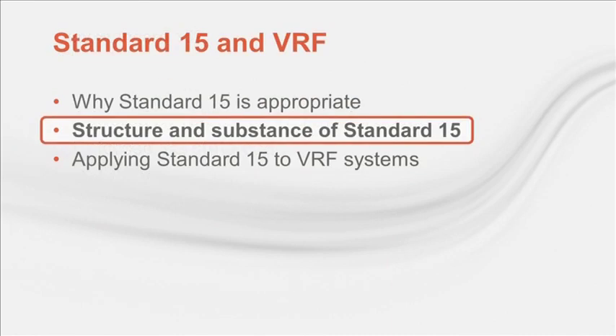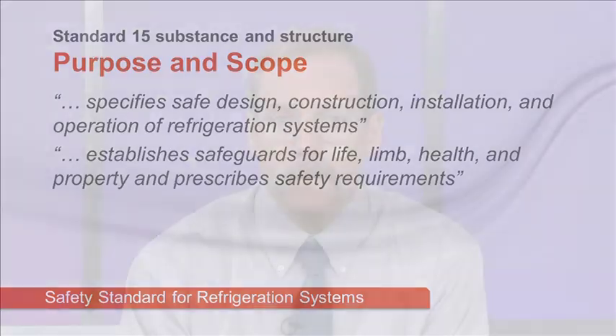Okay, so once you establish that Standard 15 applies in your jurisdiction, the next step is to look at what Standard 15 requires. A good place to start is with the purpose and scope. Notice the focus on safety. In fact, the name of the standard is Safety Standard for Refrigeration Systems. The material in this standard is intended to promote safeguards by establishing a framework to guide the design of refrigeration systems. Keep this focus on safety in mind when you read the standard. If you're confused about how to interpret a particular section, choosing the path that results in greater safety will generally lead you in the right direction.